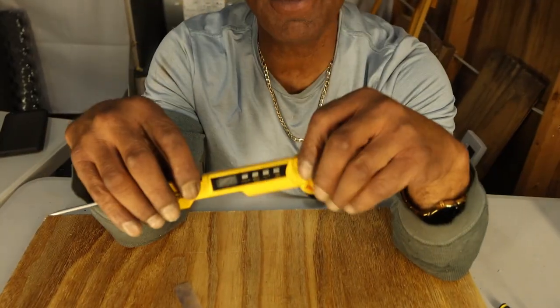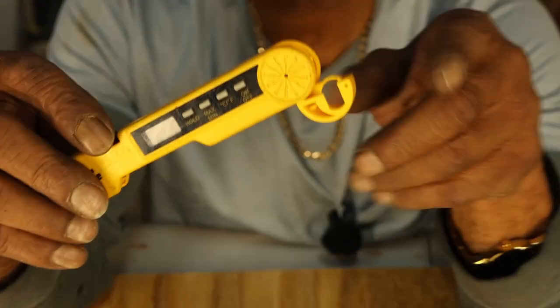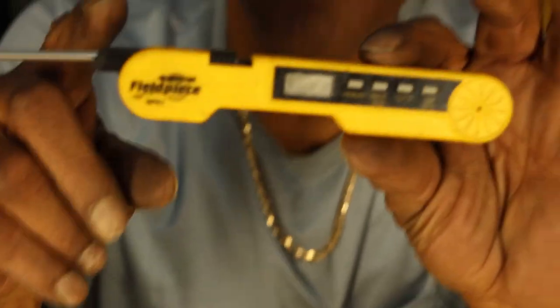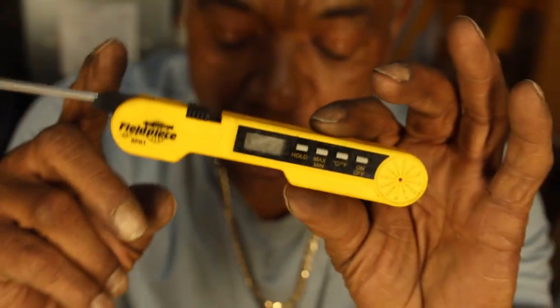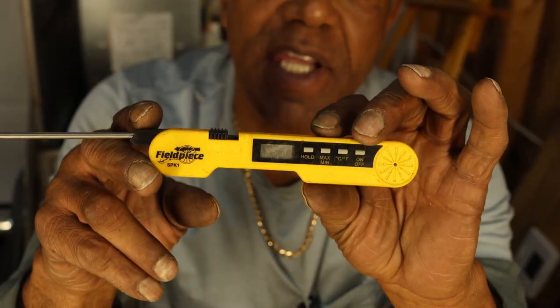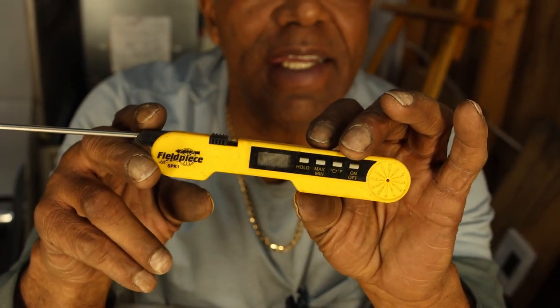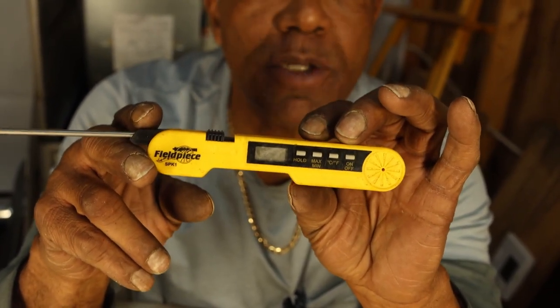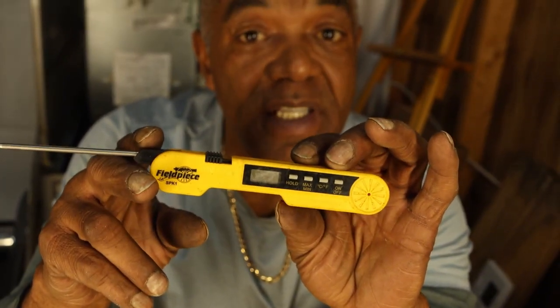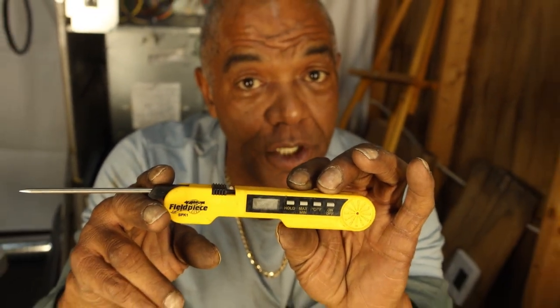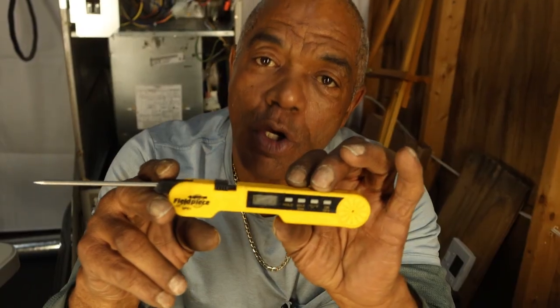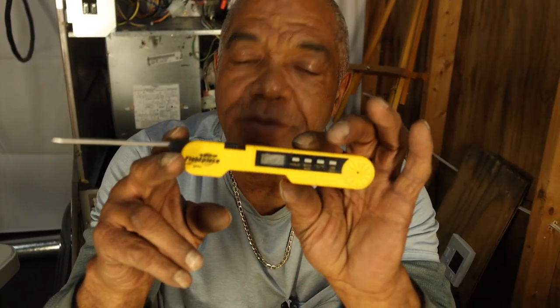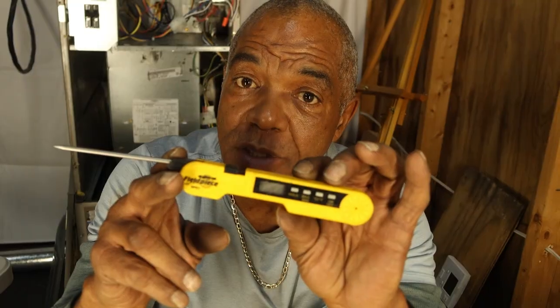There went that battery. Good thing it ain't no good. But flip it open, little battery, put it back, then you have your second thermometer. We need to take what we call TD readings, which is a temperature differential between the supply air coming off of the unit and the return air going into the unit. And for that, we have to have thermometers.